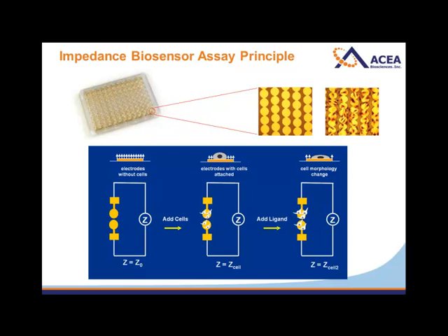And the other thing to keep in mind, and I actually didn't make this point, with our technology, there's a single electrical connection for each well. So we're averaging the impedance across the entire electrode array. So we're measuring at a population level what's going on average with all these cells. It works out to about between 70 and 80% of the surface area. So that's an important other aspect of this. We're looking at very subtle changes that are averaged over the entire population of the cells.